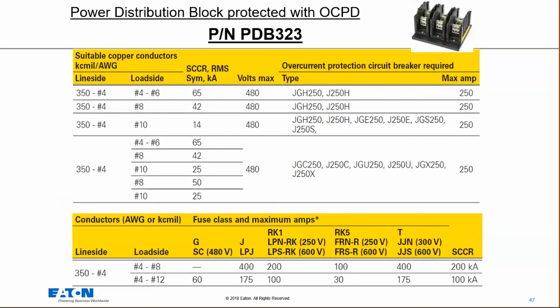But if it's unmarked, you obviously want to investigate it. If it doesn't have the spacing, it's pretty clear right away. When you see there's tons of space on there, you still want to make sure it's a listed device, right? You still want to make sure that when the inspector or your UL guy comes, he sees it. Otherwise, it's probably going to be a 1059 device that would have to be used in a branch application. But you still want to make sure it has that recognized component to it.